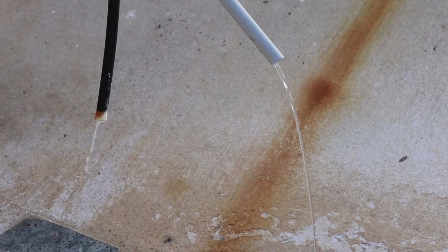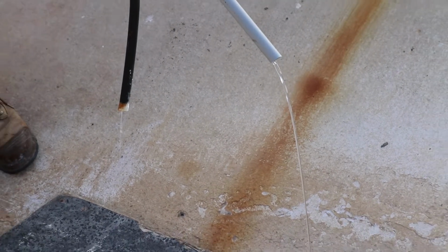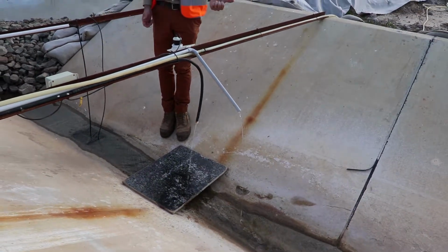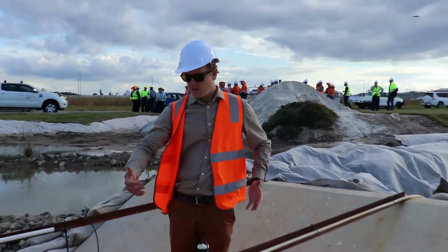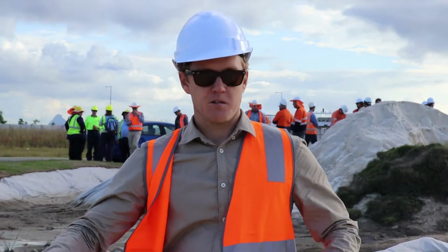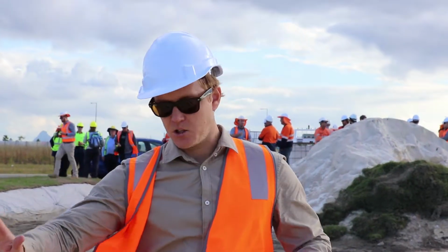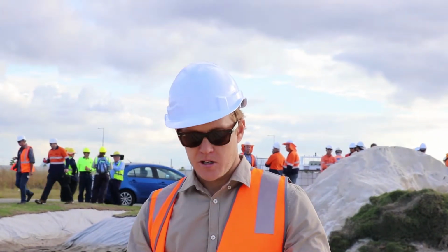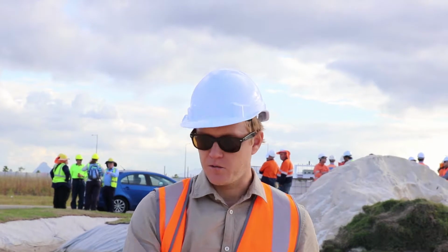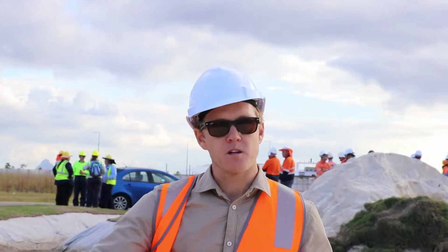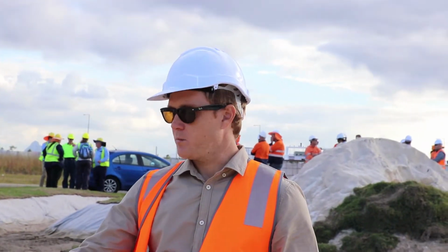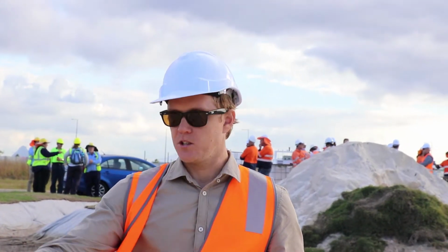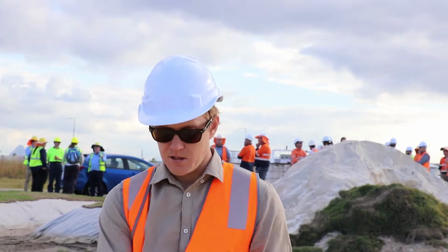So what we're measuring when we're coming here, we're converting basically that depth back to a flow. So it's all built around, for those that do hydraulics, I guess, your channel shape and what it's aligned with. The downside with these systems, the flow-activated, is you need to have some kind of measuring device. It'll usually be a pipe, could be a weir, could be a channel like this, but you need something formed that this can measure off.